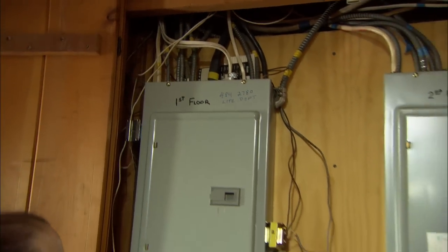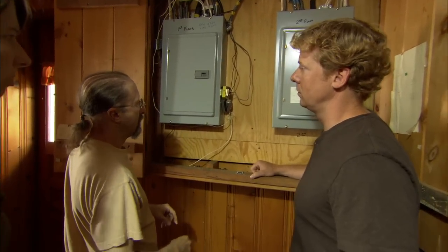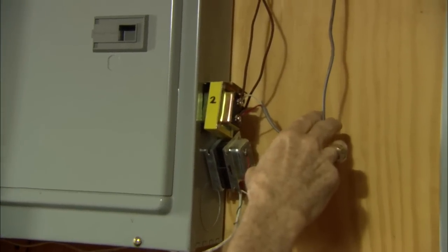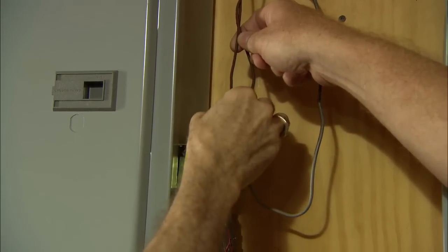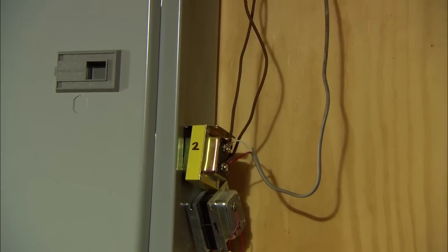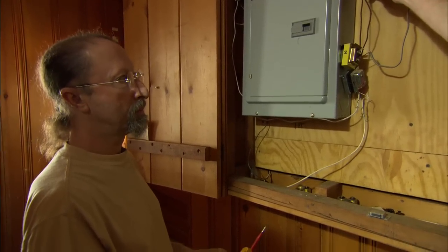Let's see what they did here. Two panels — two family house. And here are the transformers. Why are there two transformers? One for the first floor doorbell and one for the second floor. And here's what we'd expect to see: a cable going up for the doorbell. And why the second cable? They're to run some other low voltage system — an intercom system, a door buzzer to unlock the front door from upstairs, something like that. So now we have to figure out which one of these goes up to the doorbell wires that we found.